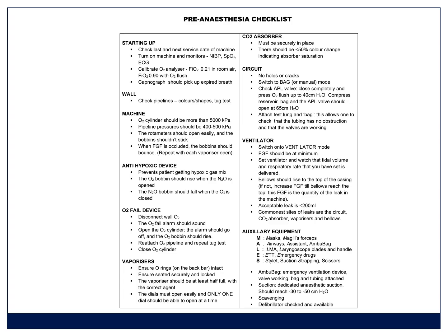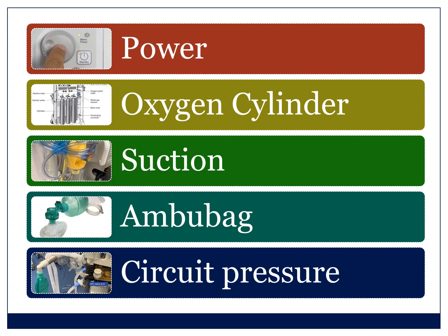Remember that you can use these checklists. You'll see that all the things that I've mentioned, they're on this list. So just put it on the side of the machine or on the wall and use it when you're checking. And don't forget, if you're not going to do the full check, at least check these things: power, oxygen cylinder, suction, ambu bag, and circuit pressure.